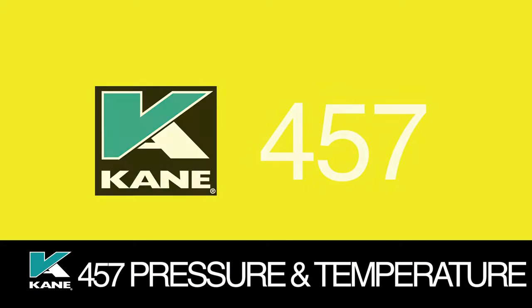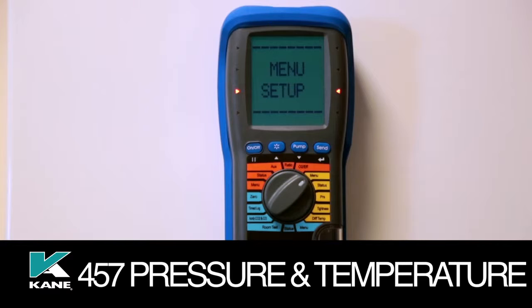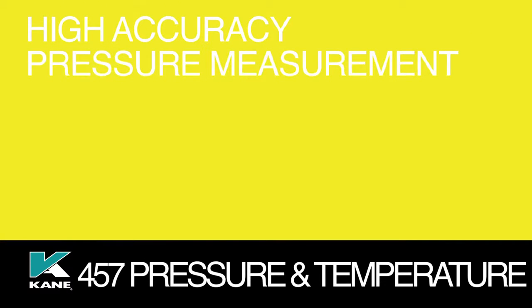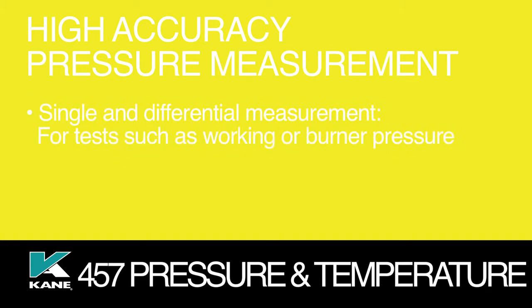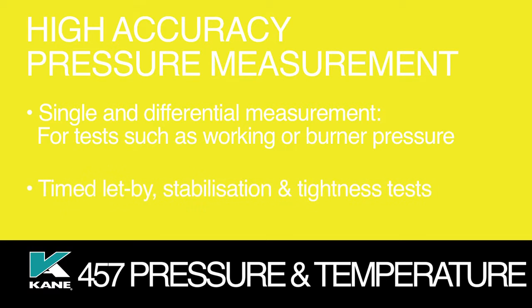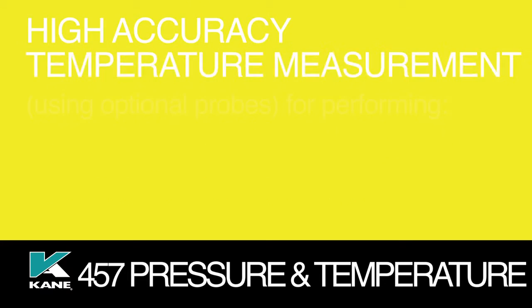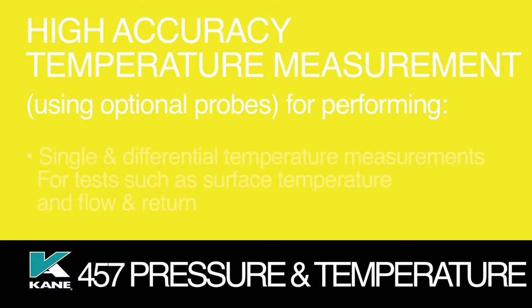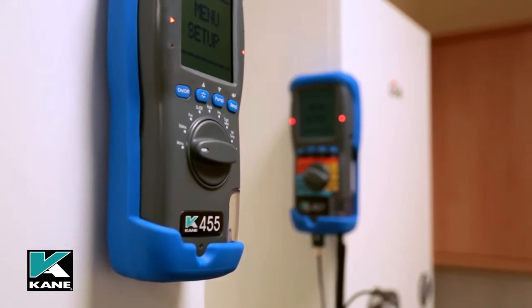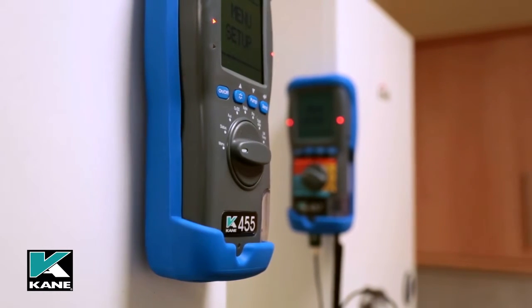Rotating the dial into the yellow section accesses the differential temperature and differential pressure measurement function, combining high accuracy pressure measurement for performing single and differential measurement, for tests such as working or burner pressure, timed let-by, stabilization and tightness tests, with high accuracy temperature measurements using optional probes, for performing single and differential temperature measurements for tests such as surface temperature and flow and return. This section also operates in exactly the same way as the KANE455.